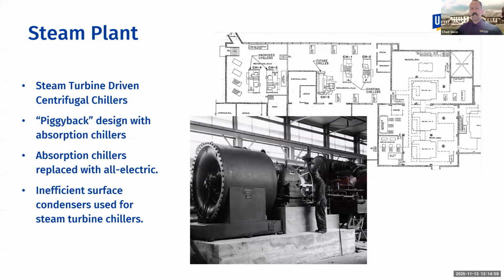Up until the 80s, the plant utilized two steam turbine centrifugal chillers and two absorption chillers. One of the steam turbine chillers operated in series with the two absorption chillers as a piggyback design to take advantage of the condensing. But the other chiller had a surface condenser, which really derated its output, apparently, from 1,800 tons to about 900 to 1,100 tons.